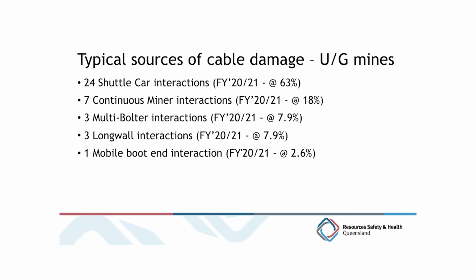As you can see, shuttle cars form the highest amount of cable damage, with 63% of underground trailing cable HPIs last financial year, with operators misjudging turns, inadequate or poor protection of cables on the rib, poor roadway conditions causing build-up of coal and debris in the reelers. And another favourite of mine is backspooling. And the normal excuse of why it occurred is that the operator was not paying attention at the time. I've got a simple solution to this: don't backspool.